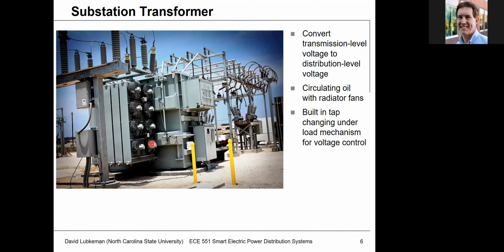There's circulating oil through the transformer, and the fans help cool that oil. This is why transformers typically have multiple ratings: one rating with no cooling fans, and then the fans are usually broken into two or three banks — as you turn more fans on, you increase the rating of the transformer.